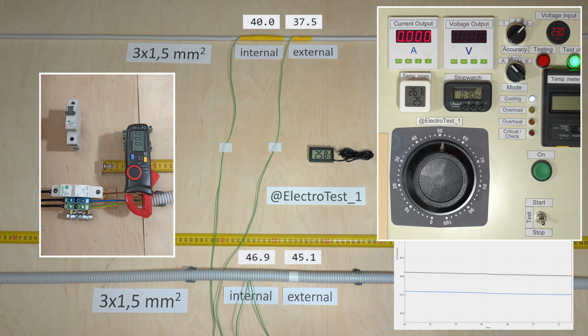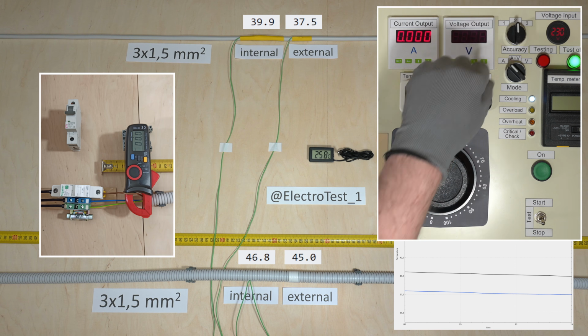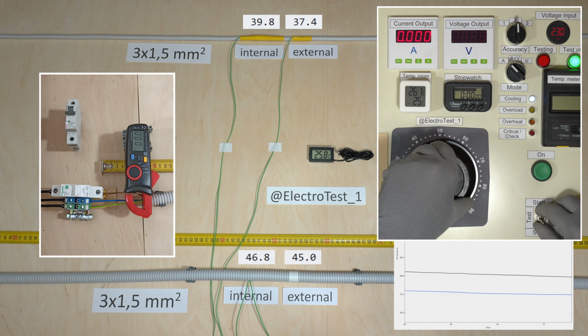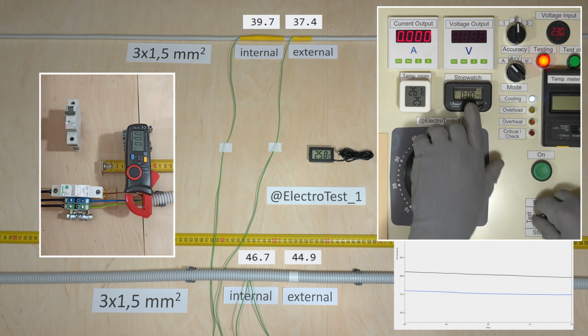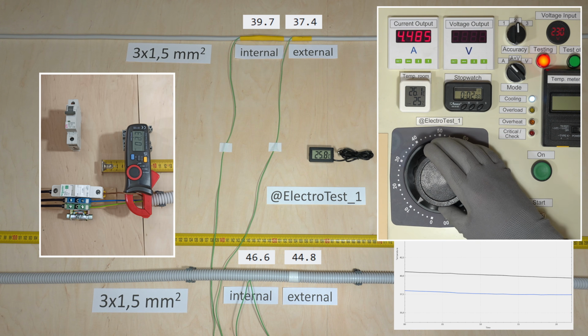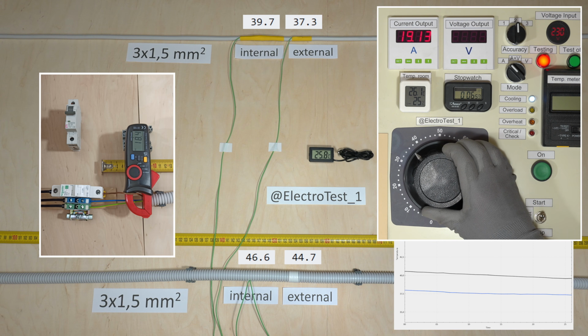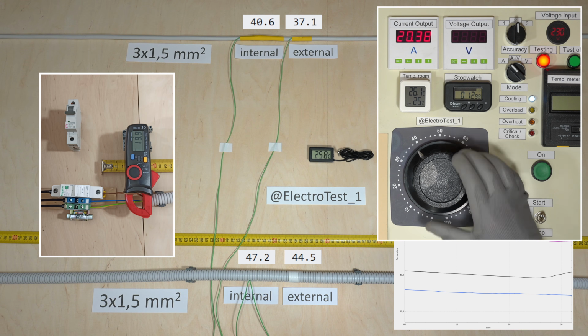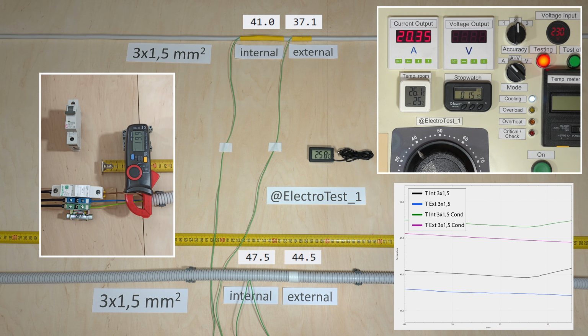Testing at 20 amps. A current of 20 amps is an overload for a 3 by 1.5 cable. The cable is protected by a 16 amp circuit breaker, so eventually it should trip. However, with a 1.25 overload factor, the breaker may not trip for a very long time.